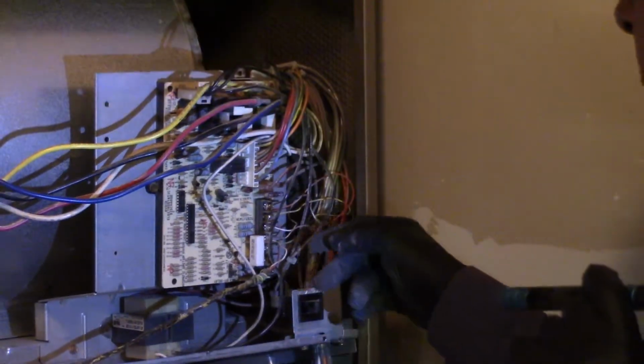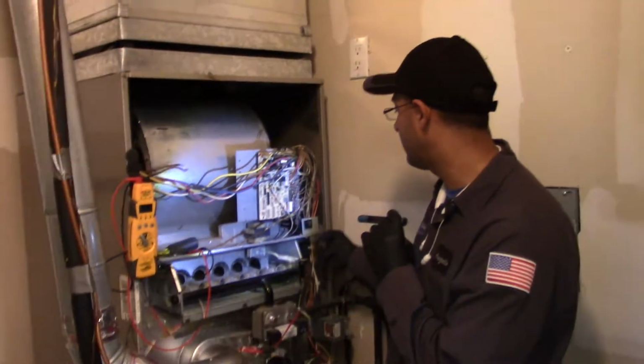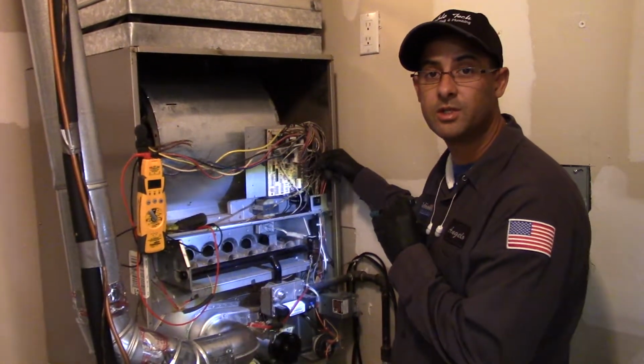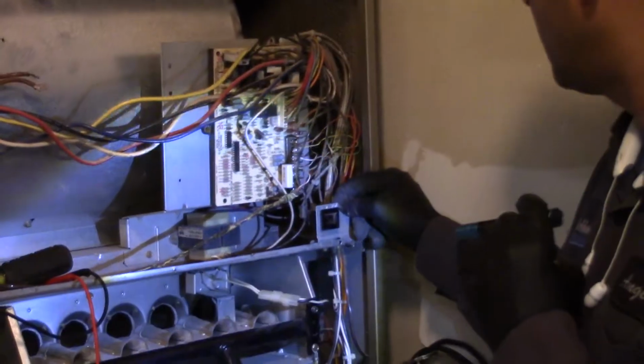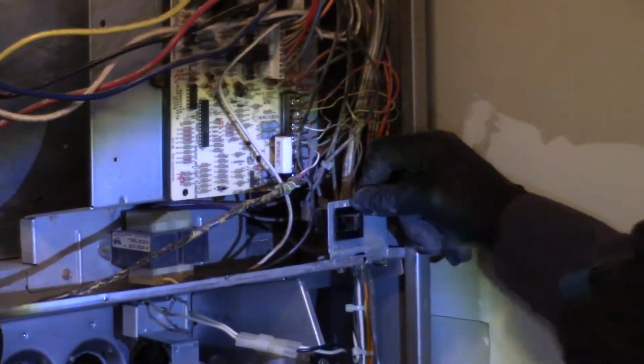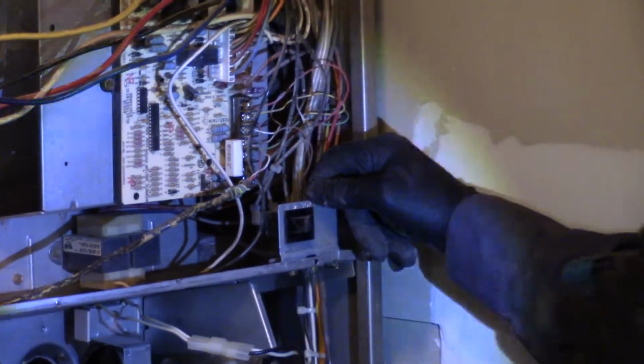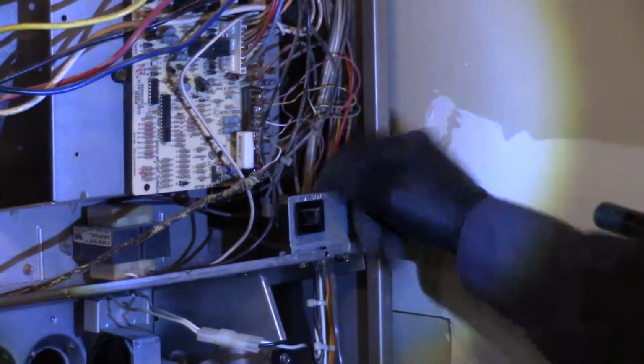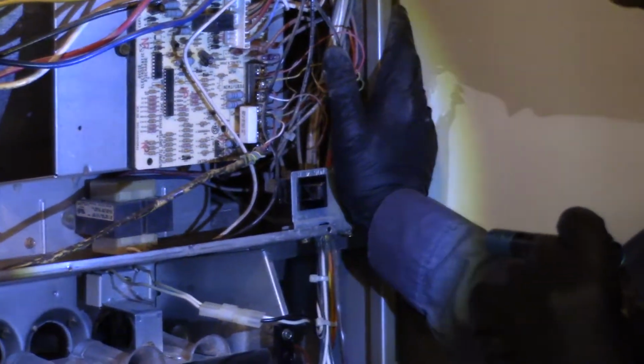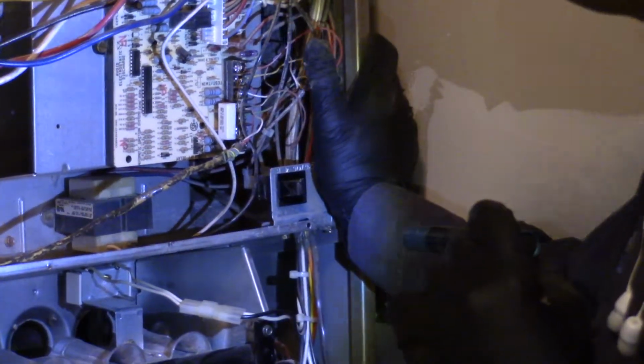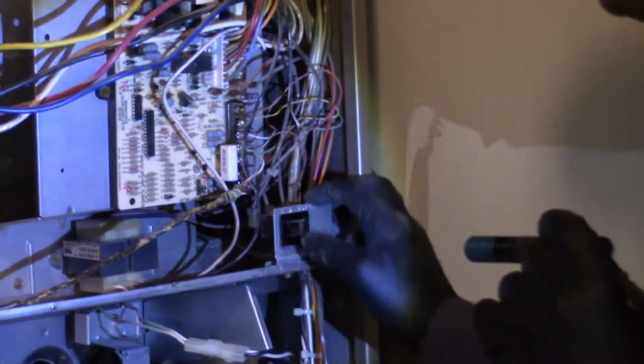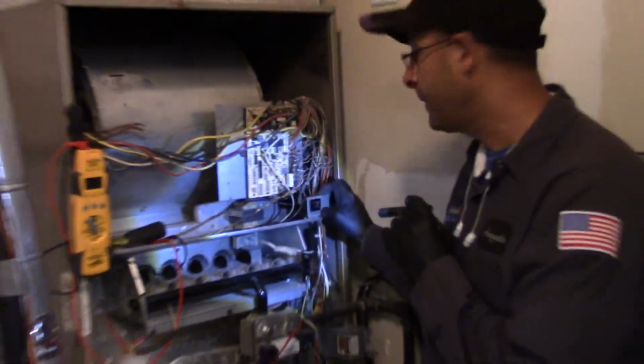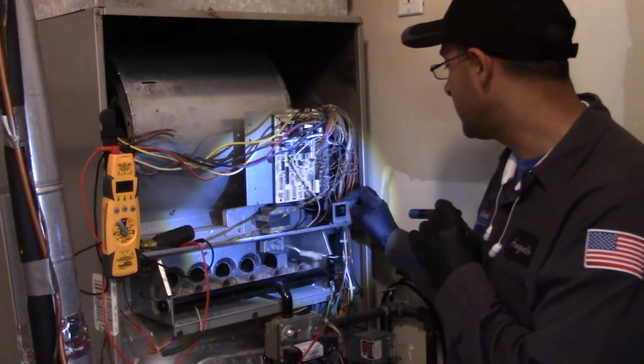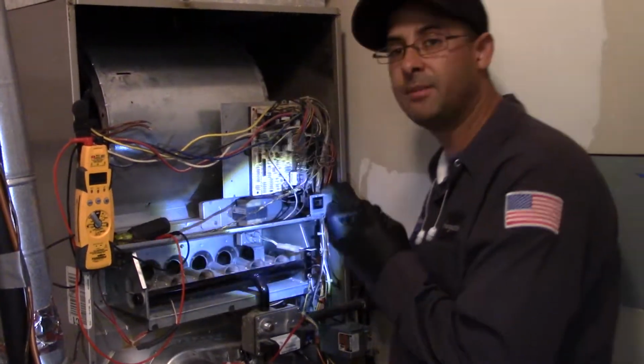So the power comes in from the outlet into the furnace. It goes through this door switch, okay? This door switch stops the power and allows the power to pass over into the furnace. So once we put this panel on, the door switch says it's safe to operate. There's no homeowner that has their hand in here and their hand's gonna be sucked in there. So it's basically a safety switch so people don't get hurt. So when the door panel is open, it stops all the power to the furnace.